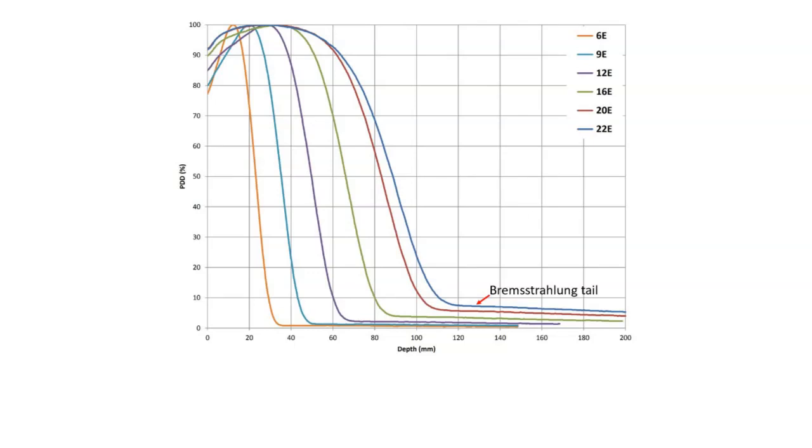A couple general rules with electron beams. One is that the range is roughly equal to the energy divided by two. So R stands for range here, and you just take your beam energy in MeV and divide it by two, and that should approximately give you the range. So if you look at this 6E beam here, this orange curve, six divided by two is three, and you can see that the range is about three centimeters. So it's just a general rule. And it really comes from the fact that electrons lose about two MeV per centimeter in water, or human tissues, roughly water equivalent.